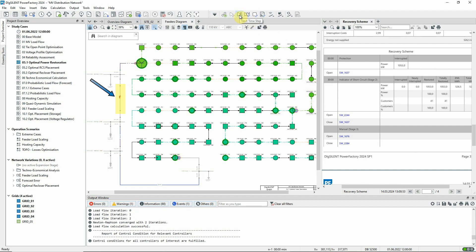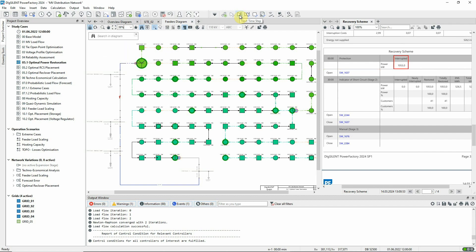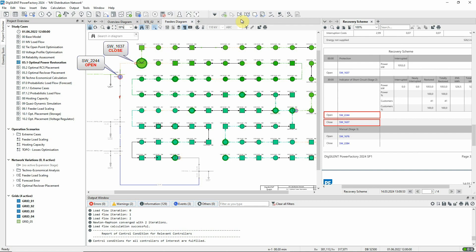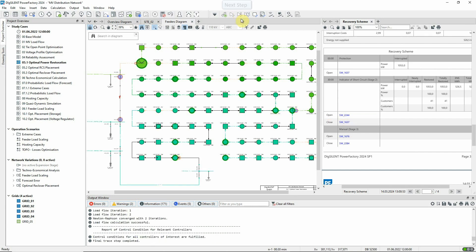Now the fault has occurred and circuit breaker SW1637 in substation 2 has opened to clear the fault. This leads to a loss of supply of 1053 kilowatts. In the next step SW2244 opens, which then allows SW1637 to be closed again. In the final step SW1676 is opened on the other side of the fault to complete the isolation of the faulted equipment. And SW2284, which was previously open and formed a tie open point, is closed in order to resupply the loads, completing the process.